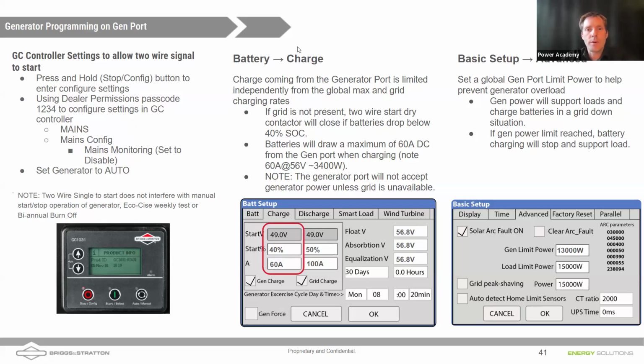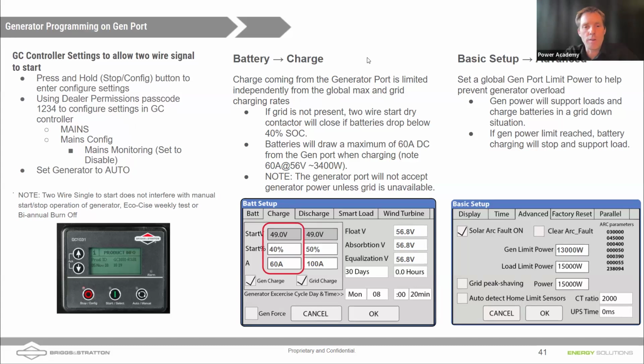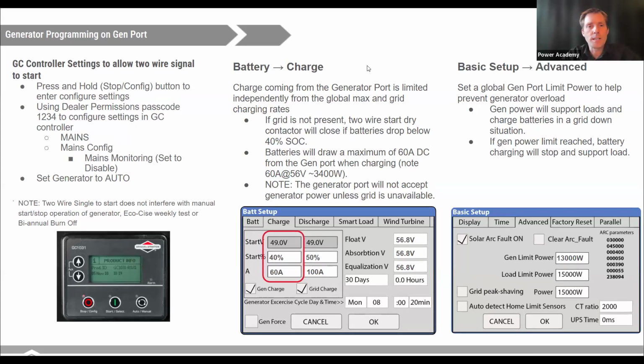The sequence of setting up the battery charging off the generator, there are a couple things to keep in mind, right? So we're only going to charge off the generator when it's on the gen port if the grid is down, right? If the grid is there, we'll charge off the grid first. So as we mentioned before, this amperage for pulling from the generator is DC amperage, right? That's the batteries, that's the amperage going into the batteries during charge.